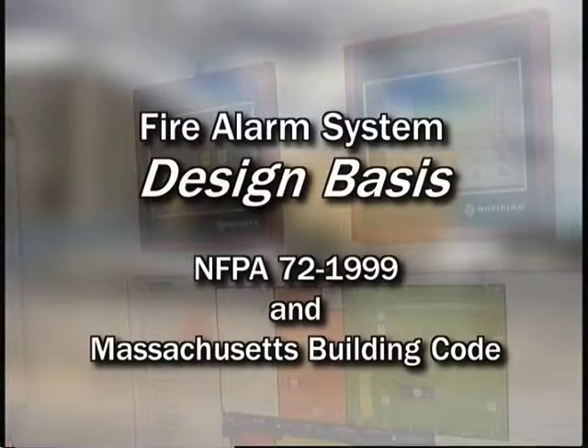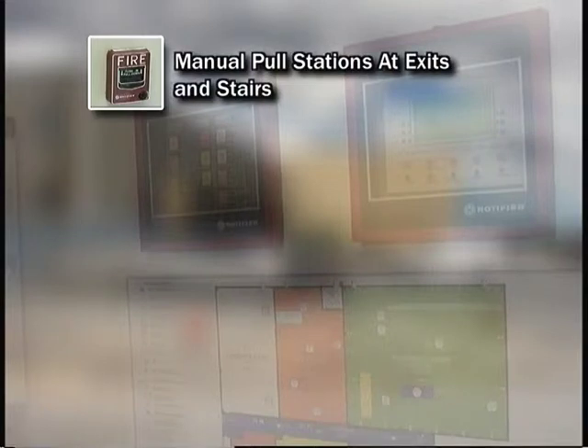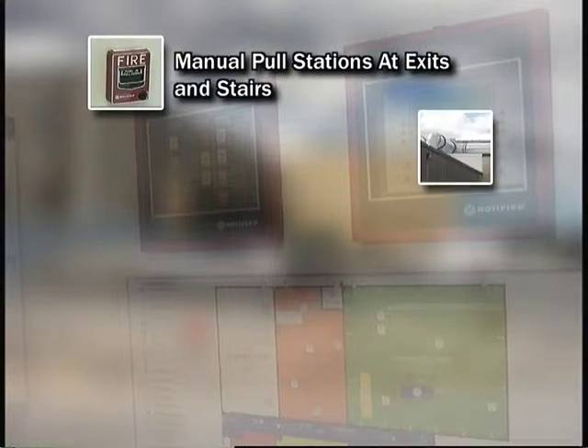The basis for design for the fire alarm system includes compliance with NFPA and the Massachusetts building codes. The system provides manual and automatic operation with on-site audio and visual alarms to indicate a fire event within the building. The fire alarm system includes manual pull stations at exit discharge locations and top-of-stair locations, as well as any corridor areas where travel distance to an exit is 200 feet or more.